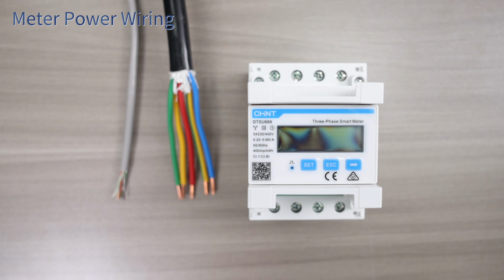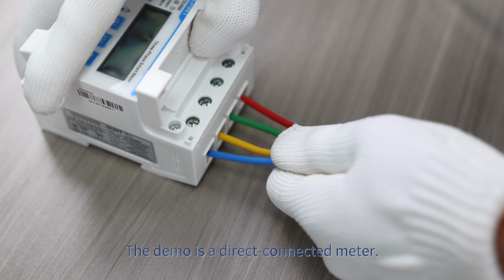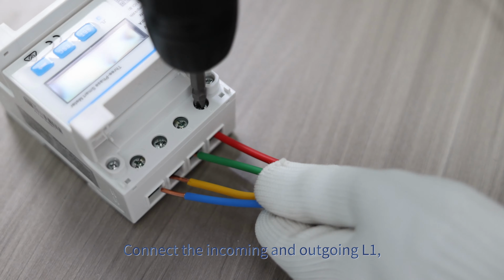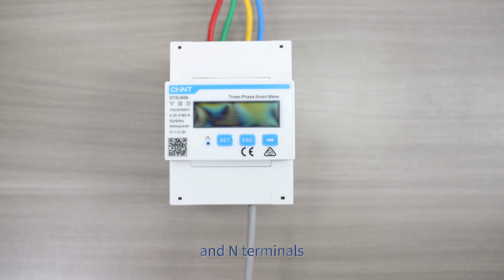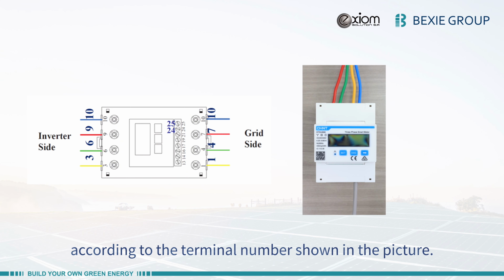Meter power wiring. The demo is a direct connected meter. Connect the incoming and outgoing L1, L2, L3, and N terminals according to the terminal numbers shown in the picture.